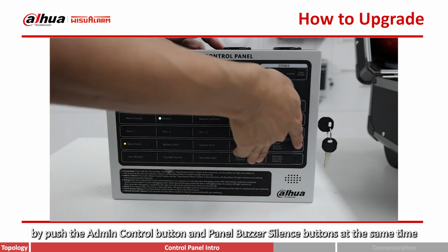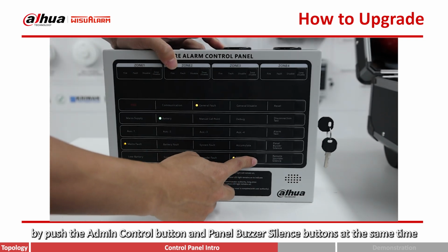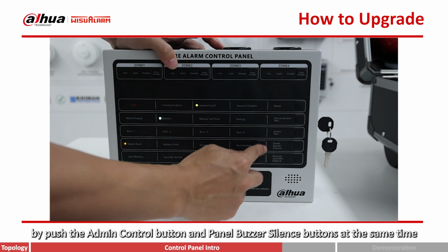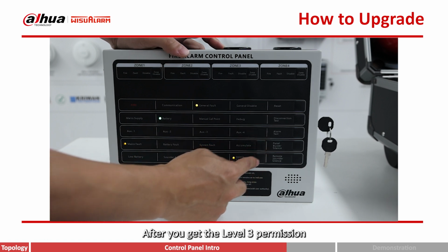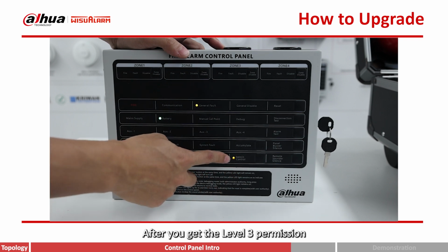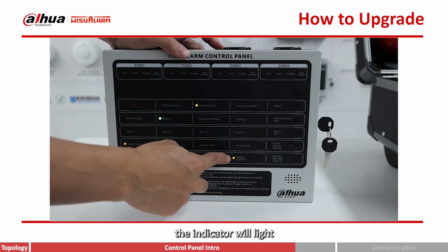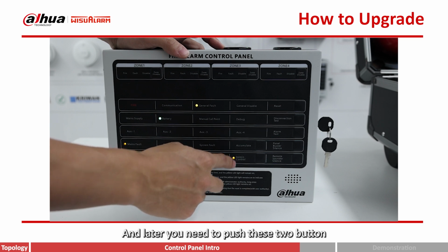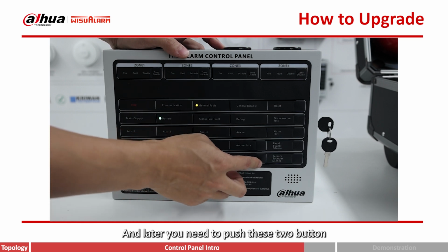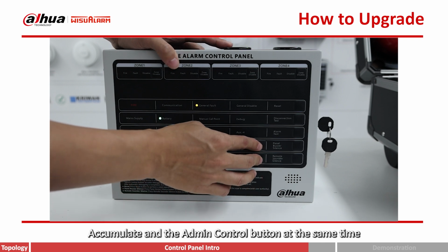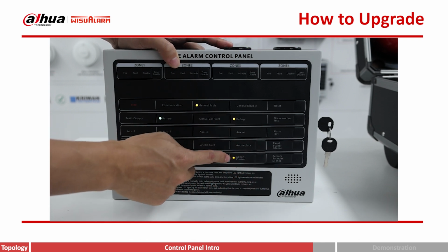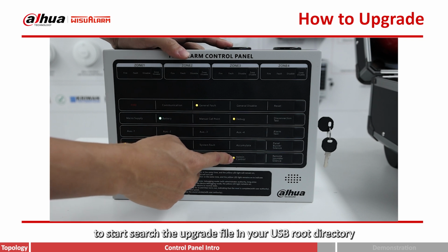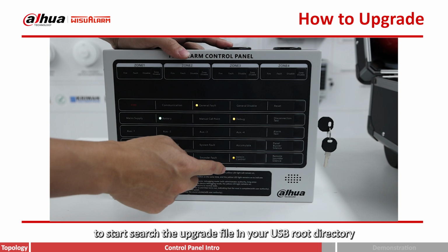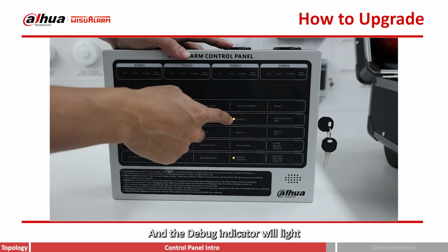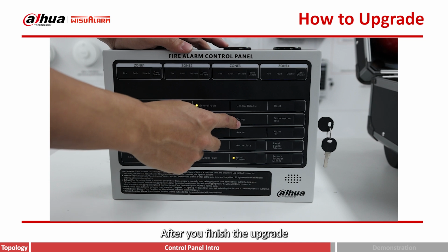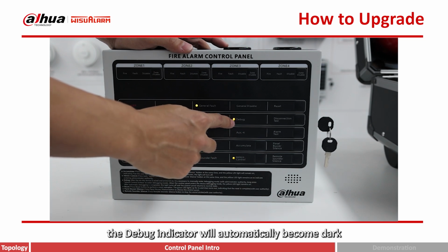By pushing the buttons admin control and the panel silence in the center, after you get the level 3 permission, the LED light will light. And later you need to push these 2 buttons, accumulate and admin control, in the center to start searching for the firmware in your USB root, and the debug light will light. After you finish the upgrade, the debug light will automatically go dark.